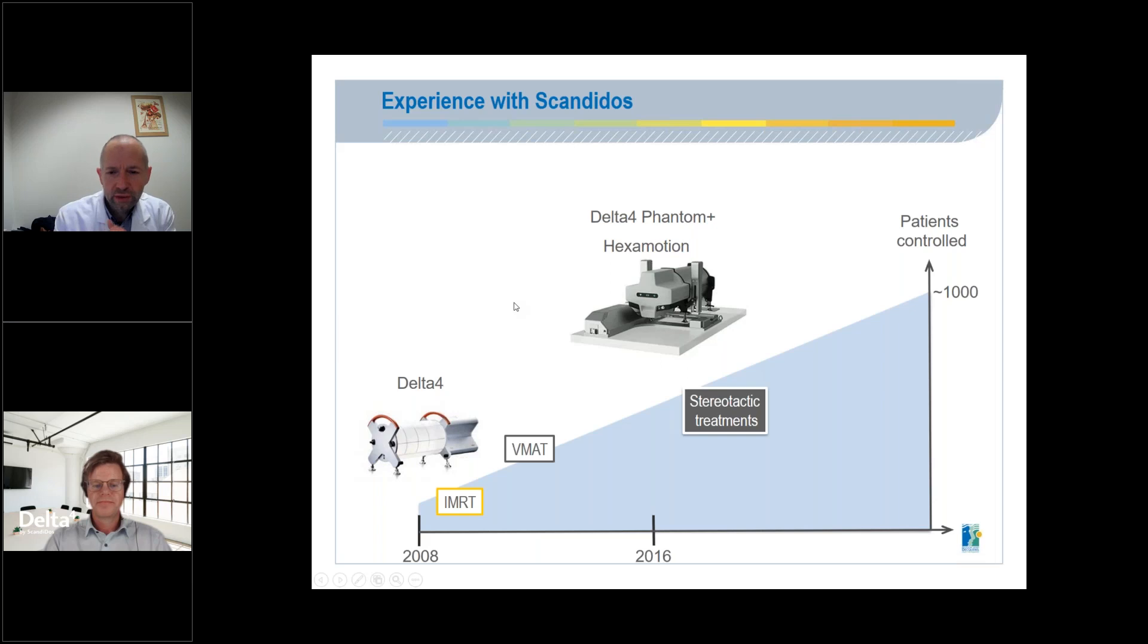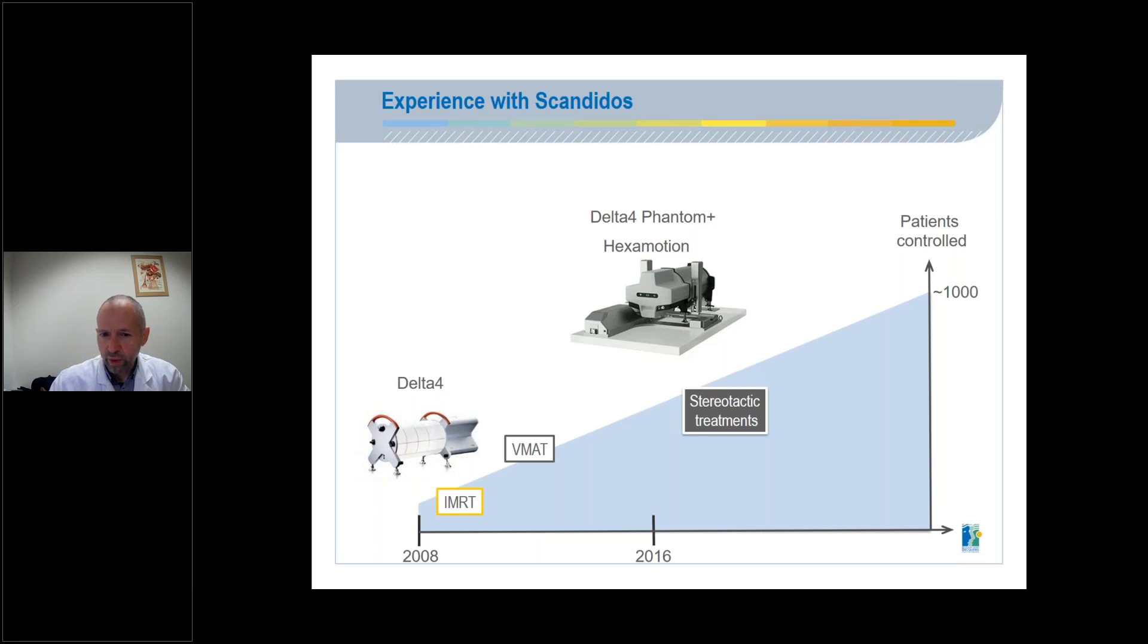What is our experience with Scandidos? In 2008, we bought the first Delta IV in order to control IMRT and VMAT treatments in our departments. In 2016, we replaced Delta IV with a new version, the Delta IV Phantom Plus. Compared to the old Phantom, this new Phantom is easier to use because it is wireless and the calibration procedure is simplified.